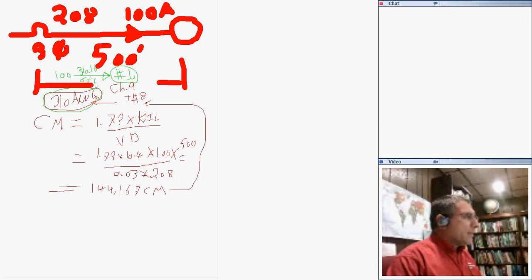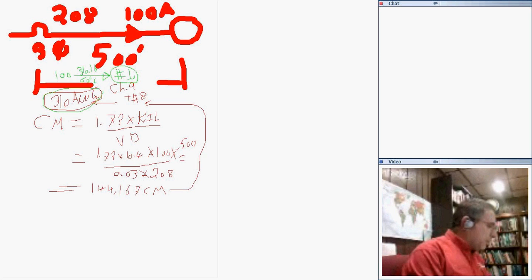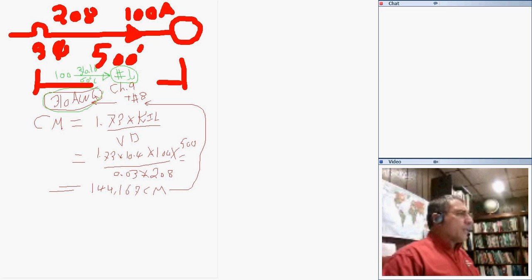Agree with 3 aught. So exercise, guys, when you do voltage drop calculation, and you do good load and you do derating, you're going to pick up the conductor that gives you the largest size. If you're sizing a conductor, you're going to pick up the largest size conductor based on voltage drop or based on basic sizing. Any questions, guys, about this problem?